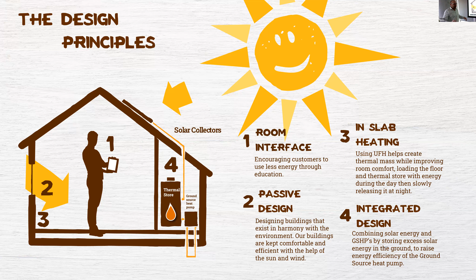This is pretty much the basic design of how we work the system. We've got our collector bores down the bottom here. This is our set of bores, and they come up and feed direct into the heat pumps. Then we've got solar arrays coming through a heat exchanger. The solar arrays were going direct to the hot water tank, but we did have a heat exchanger in line. The purpose of that heat exchanger is for when we had excess solar, so the solar had already charged the hot water tank. We would kick this exchanger in with a little pump, and that would take that excess solar and load it down into the bores, into the ground. The purpose of that was to charge the ground prior to wanting to pull the heat out at night.